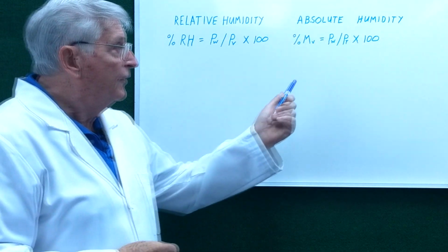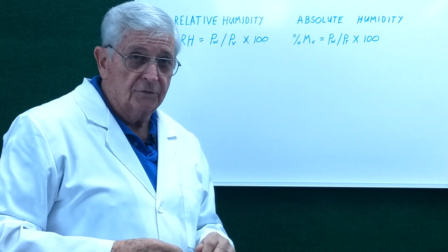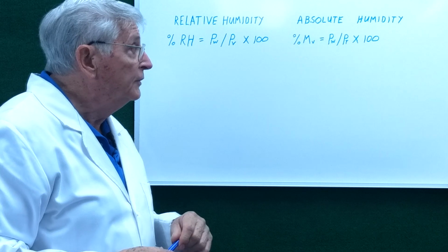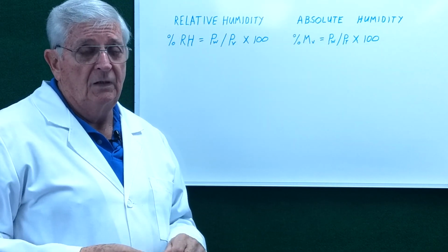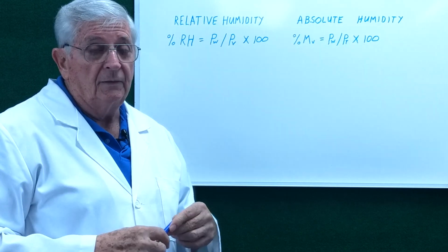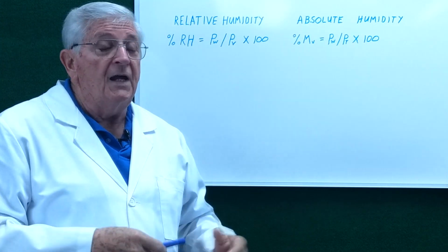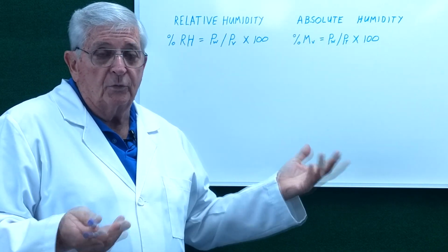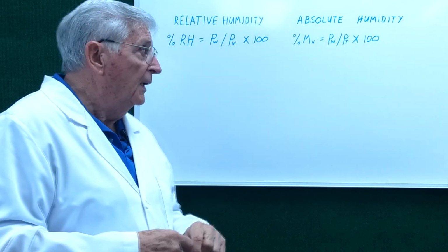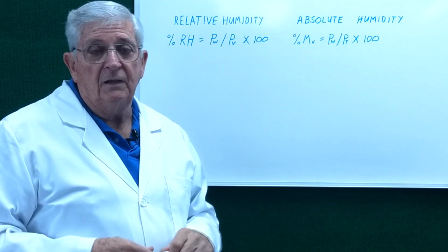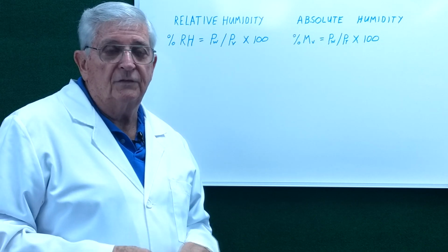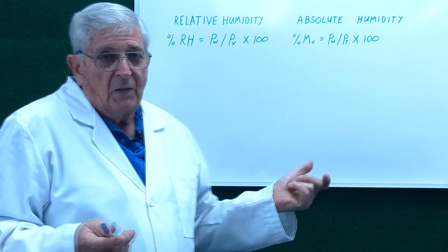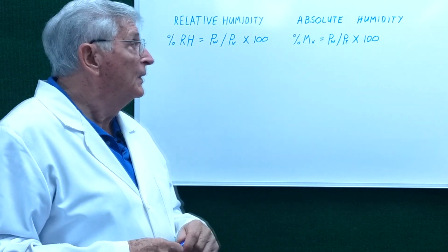Now, one of the absolute moisture scales that we showed was the percent moisture by volume. And to me, this is the most intuitive of these scales. Again, just as we say in the atmosphere we have 20% oxygen, we can talk about the percent of moisture. And typically in a room where temperature and humidity are somewhat controlled, you have about 1% moisture by volume.